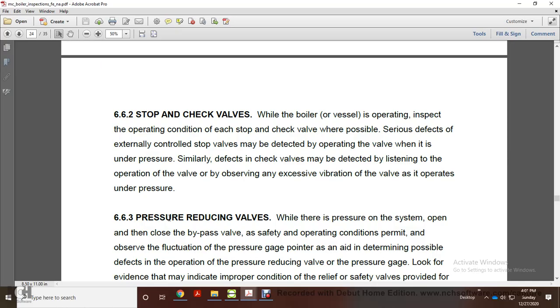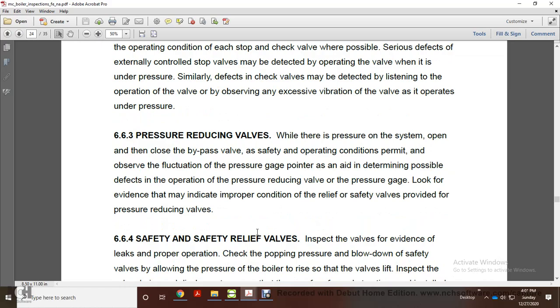Similar defects in check valves may be detected by listening to the operation of the valve and observing any excessive vibration of the valve as it operates under pressure. 6-3, pressure reducing valve. While there is pressure in the system, open and then close the bypass valve. If operating conditions permit, observe the fluctuation of the pressure gauge to determine the possible effect of the operation of the pressure reducing valve. Look for evidence that may indicate an improper condition of the relief or safety valves provided with the pressure reducing valve.